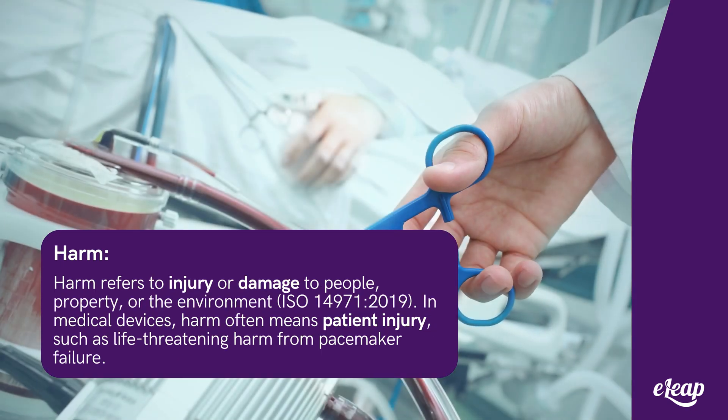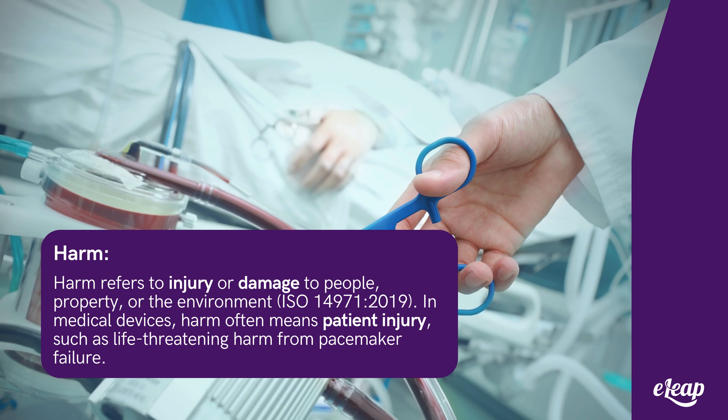Harm refers to any injury or damage to people, property, or the environment (ISO 14971:2019, clause 3.16). In the context of medical devices, harm typically refers to injury to a patient or user. For instance, harm caused by a malfunctioning pacemaker could result in life-threatening conditions.